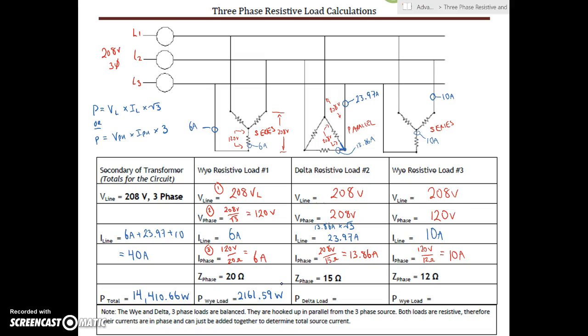Now, if you're looking at the answers that I have on the website, they're a little bit different. I'm using a different calculator today, and I'm using the full root 3, not dropping it down to 1.732. So the values here in this video will be slightly different than what you'll see on the answers on the website. Next one, we have 208 volts, line current is 23.97, multiply that by root 3, and that gives us 8,635.58 watts. Last one for the last Y load, it's 208 volts on the line, line current is 10 amps, multiply that by root 3, and that gives us 3,602.66 watts.